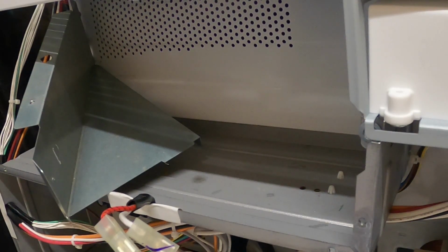But if you don't know what's going on, don't order those parts. You don't need a high voltage transformer in all likelihood, and it's very unlikely you need the capacitor if the unit runs and doesn't blow a fuse. Again, we're talking once in, I'm probably going to guess, 5,000 microwaves over my career, and that may be a light number because we used to do 10 or 15 a day in the shop when I worked in a shop where people could carry them in, back in the days when microwaves were worth something. So with that note, that covers your bad secondary voltage on your microwave.